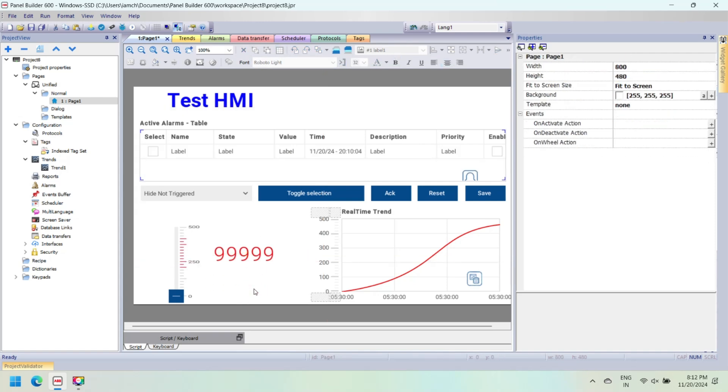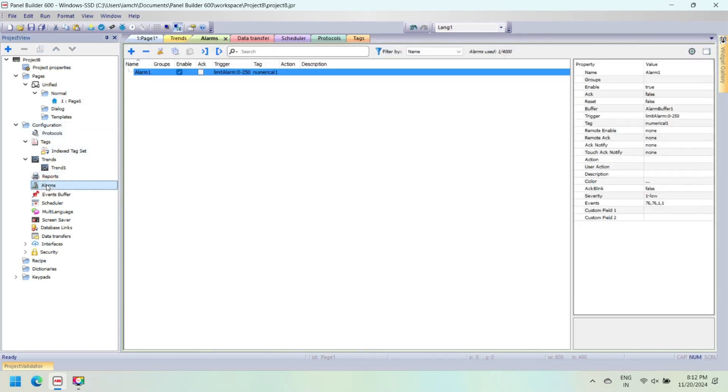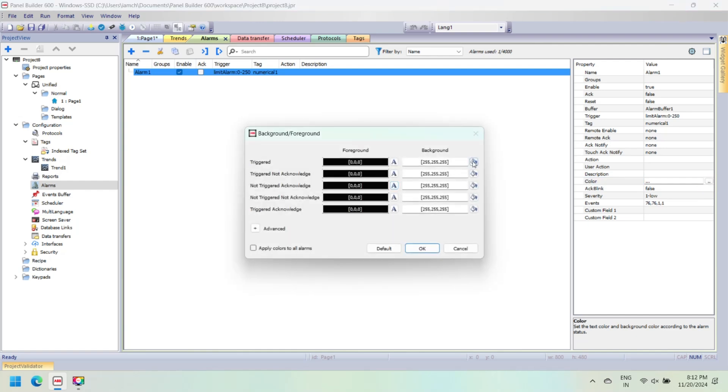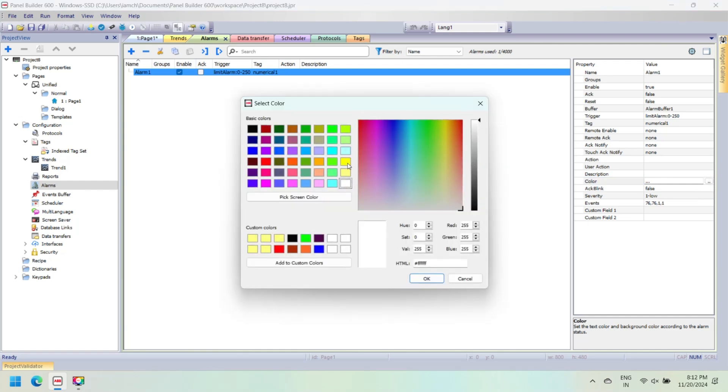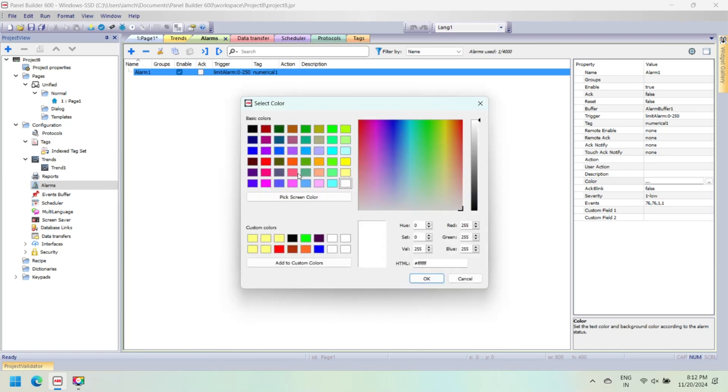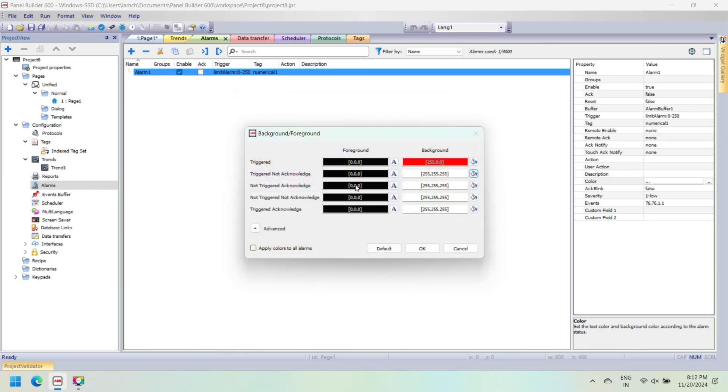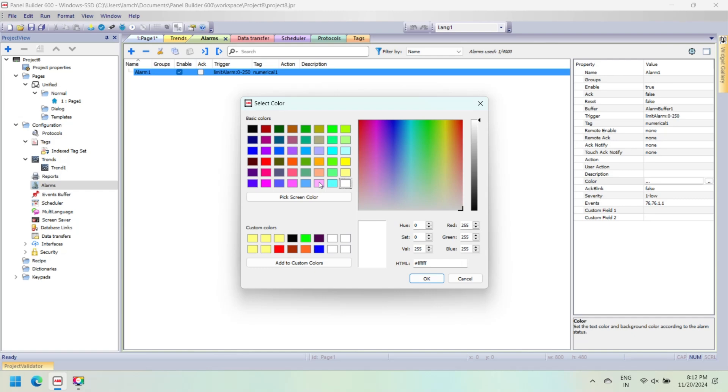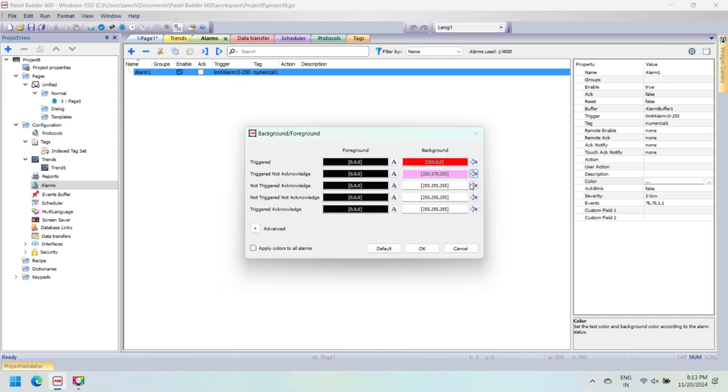In alarm properties, you can set actions which execute when the alarm is triggered. Additional conditions can be specified in the events column. Set the severity of the alarm. If multiple alarms are triggered simultaneously, actions will be executed based on severity settings. Change background color and font settings for alarms.